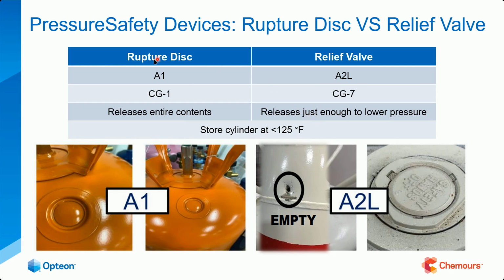The rupture disc is considered a CG1 for A1 refrigerants, and it releases the entire contents of the tank. Moving forward, for more peace of mind with A2L refrigerants, it's going to have a CG7. Think of it as a spring-loaded device, or a relief valve if you will, and it's going to release just enough to lower the pressure. My definition is it's going to burp - release just enough charge to bring it back to the safe specification, and then shut back up.